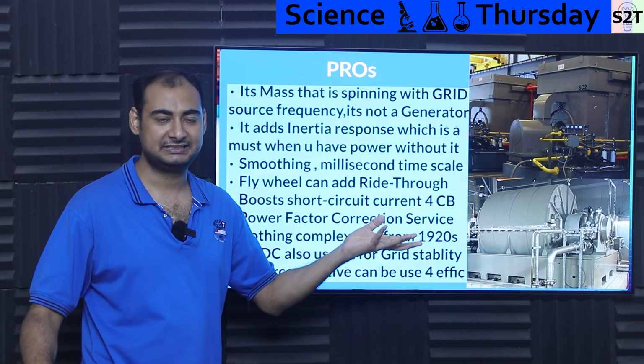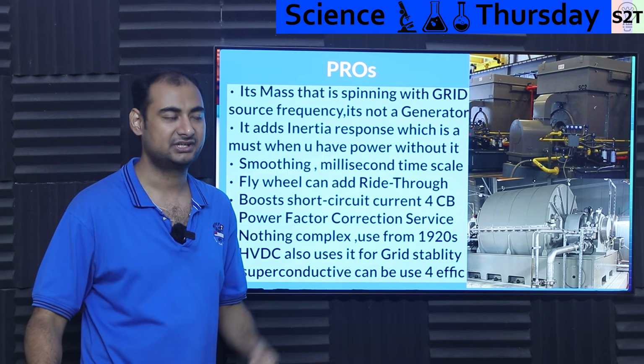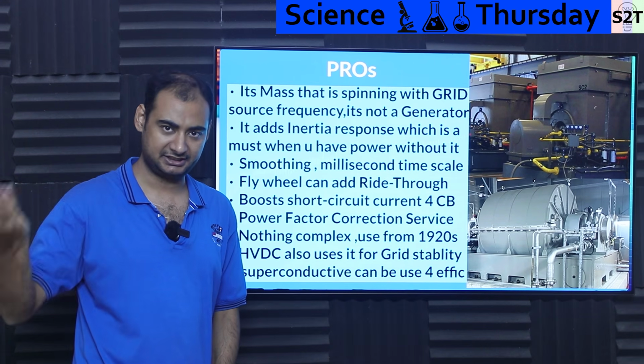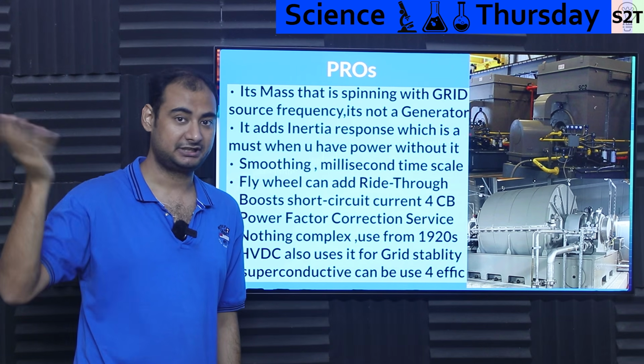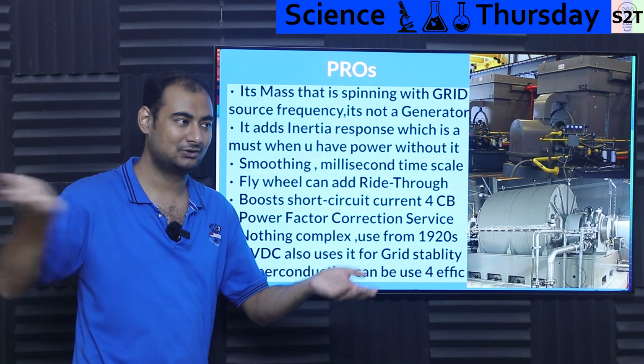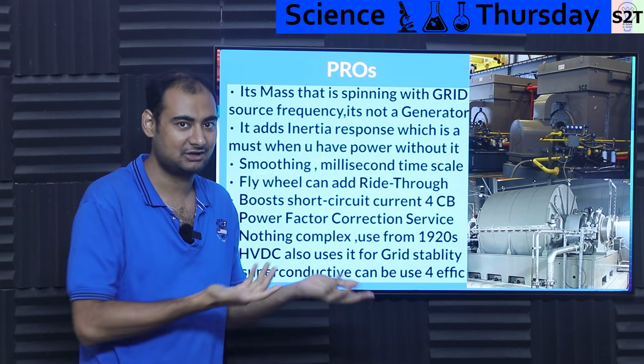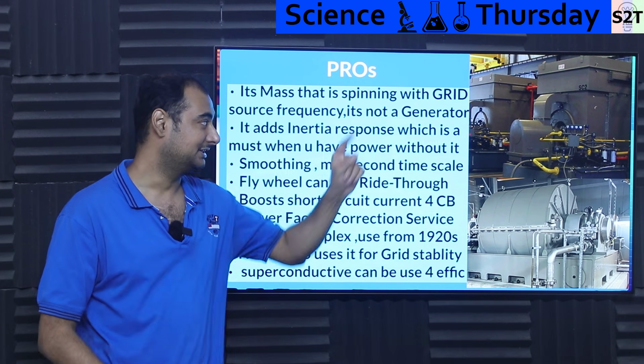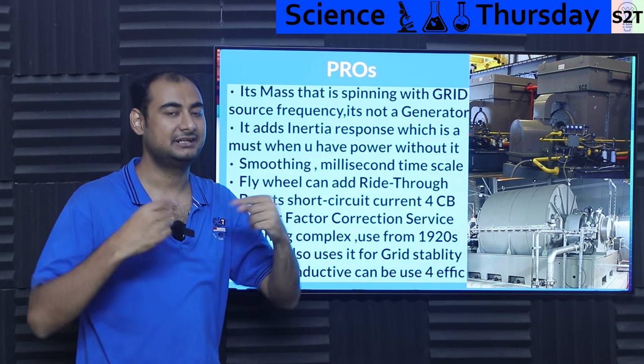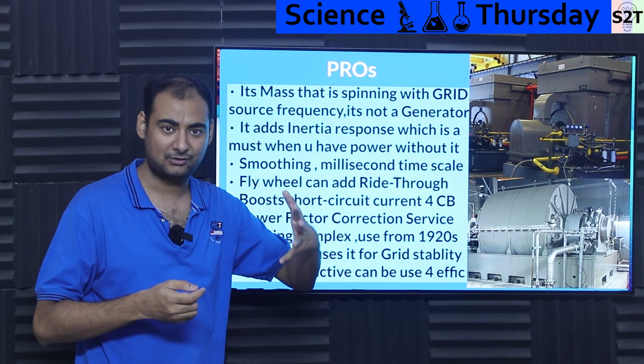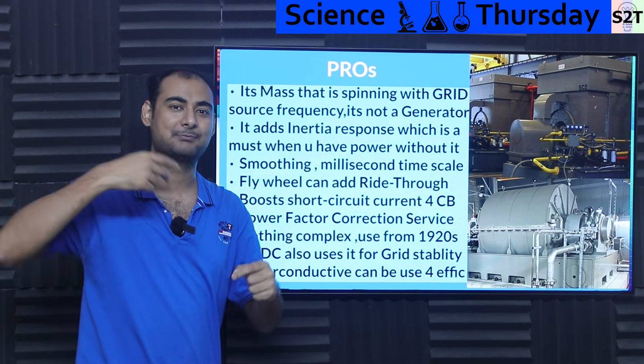The power plant only has inertia equivalent of, let's say, 100 megawatts, but your solar farm could be huge — in India, 2 gigawatts, 10 gigawatts, or 20 gigawatts. But you can't have 20 gigawatts of load on that tiny inertia, it's out of scale, out of proportion. So you put this in, and it will not create its own signal — it will take the signal from the power plant, the source, and amplify it.